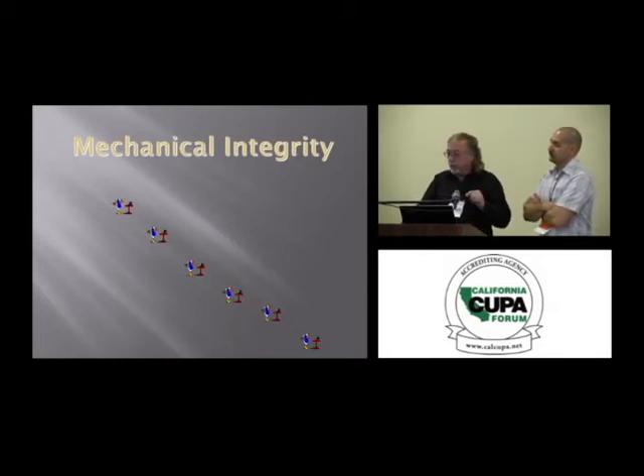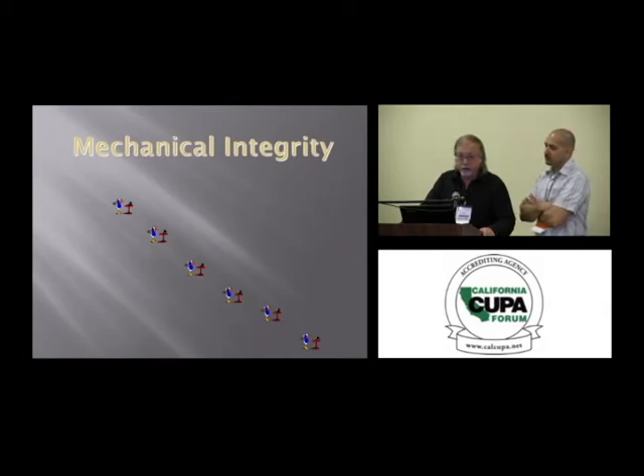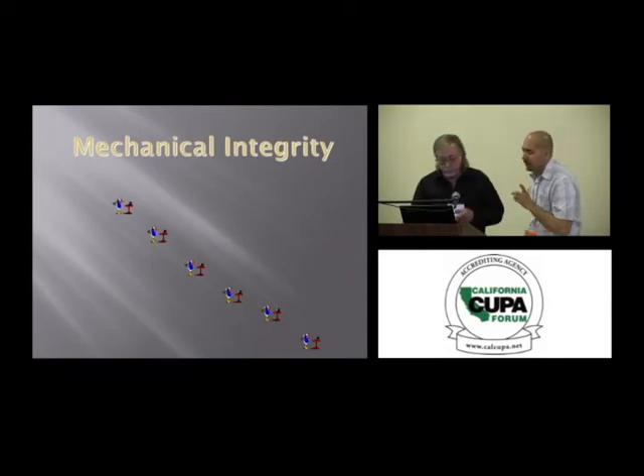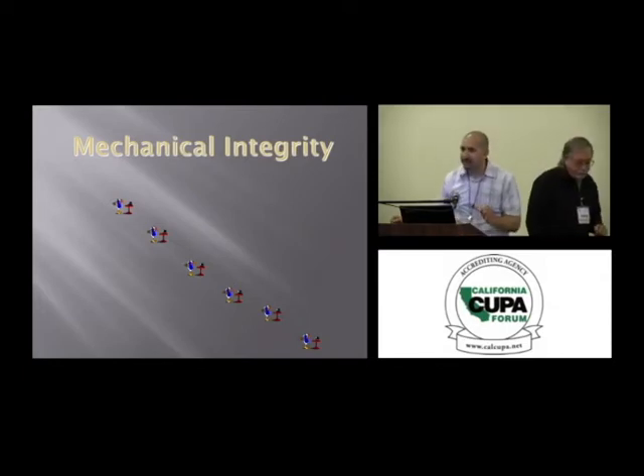But now possibly we can reduce that downwind effect affecting our neighbors, because if we're relieving to the atmosphere, we can reduce the amount that's leaving the system every minute. What we're finding is relief valves that are way too big. And what that means is too many pounds per minute. What does that do? That makes the branch lines and the headers too small. They can't support those rates of relief. In this documentation, you can go through all the calculations. There's tons of them, or you can just go and get the ANSI tables, and it'll tell you the length of the pipe, how long it can be, and the pounds per minute, and what pressure it can handle for those pounds per minute. So you don't have too much pressure drop. Go ahead. Another thing I do want to mention is it's very simple.